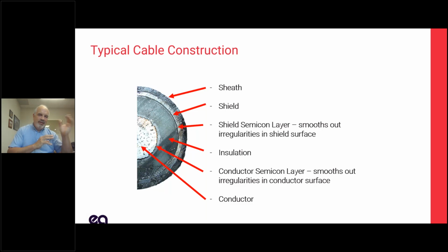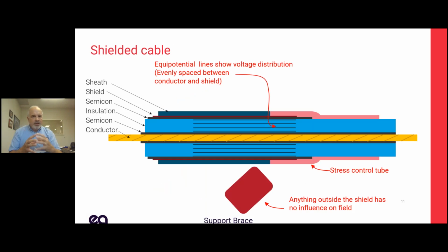So by having an even layer on the inside and an even layer on the outside, we have a nice consistent electric field between the conductor and the shield. If you look at this picture here, we've got our semicon layers, and between the semicon layers we have an electric field, and that electric field is nice and evenly spaced. Then the shield on the outside contains this electric field, and anything outside that does not affect the electric field.